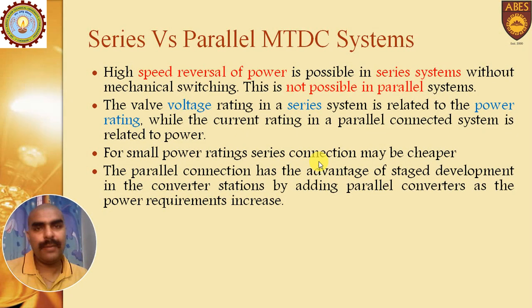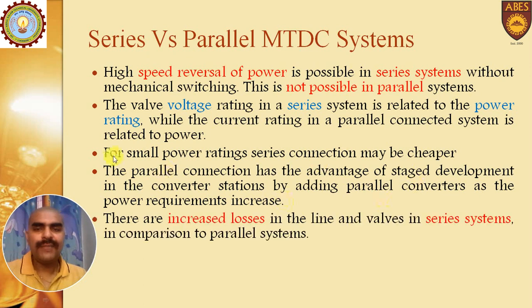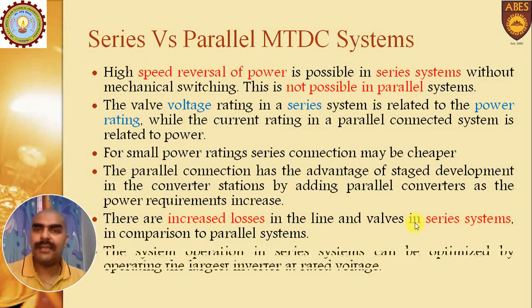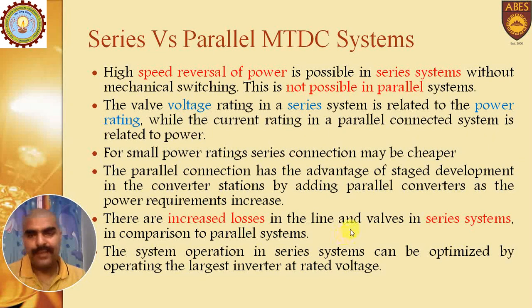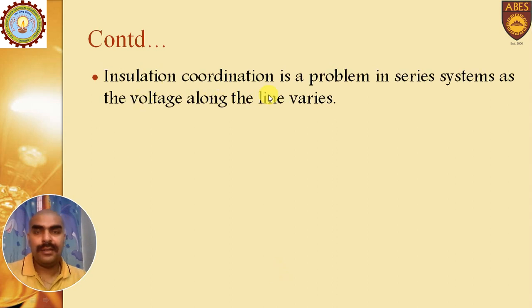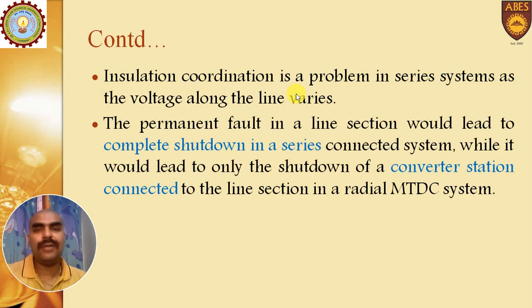Parallel MTDC system has the flexibility that we can add converter stations in parallel if power requirements increase. Then, there are increased losses in the line and valves in series systems as compared to parallel. Also, system operation in series system can be optimized by operating the largest inverter at rated voltage. Furthermore, series insulation coordination is a problem because voltage along the line varies while current is constant.